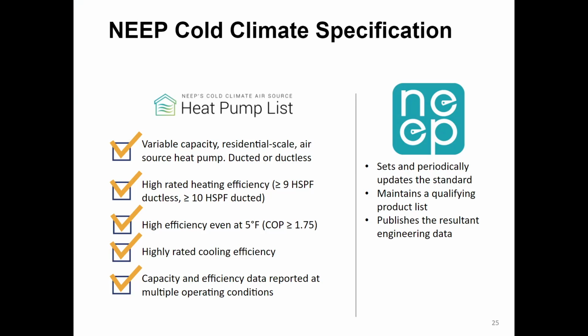The reason heat pumps are so suitable for cold climates these days is because they're able to modulate, to rise and fall with their compressor to meet the needs of the space. We can dig into the technicalities of that in a future class. What you need to know is that nothing that is not a variable capacity heat pump is suitable for cold climates. So if you ever see an on-off, non-variable capacity heat pump, do not put that in Alaska.